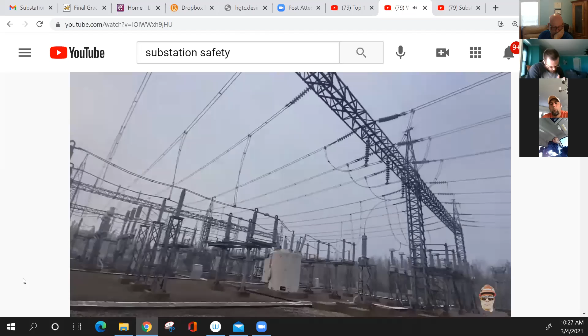Which brings me to the third and final step of what you should do whenever entering a substation or switchyard: a general inspection of the equipment. What makes our system most dangerous is when it's compromised. Everything in this subyard is bonded together - the steel building, the ground grid, all the towers, any equipment, switch handles - everything is bonded together to be at equal potential. It's just a very general inspection of the area, making sure everything's safe.